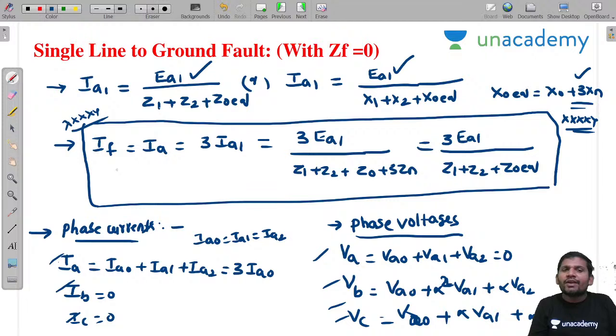A fault current equal to, because fault is at A phase, the A phase current equal to 3 times of its positive sequence component current. That's why heavy currents are flowing, because it is a short circuit fault. Heavy currents are flowing. Understood students? Please concentrate, very important. All the relations and observations are important to solve the problems.